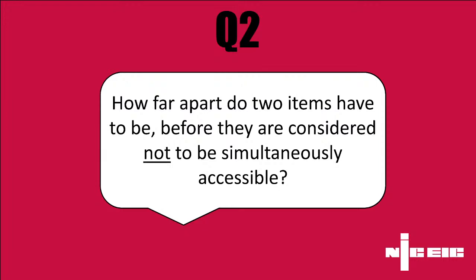So for this one, we want to go over to regulation 417.3 under the section of placing out of reach. And you'll see a distance there, which is commonly cited, often referred to as 2.5 metres. And if it's over that, it's not deemed within arm's reach. It's the 2.5 metres, so that's the key distance there. Yeah, absolutely spot on. And that's roughly, if you extend both arms out, it's effectively hand to hand, isn't it, with both arms extended in opposite directions. That's roughly where they get that 2.5 measurement from.